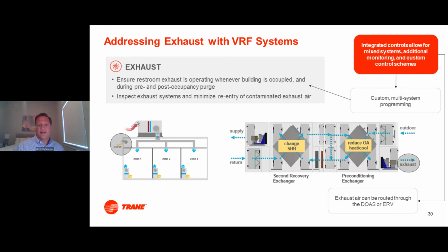When we talk about the next pillar, exhaust, how are we going to ensure that we're getting the bad air out of our building? So one piece of the guidance here is to ensure that our restroom exhaust is operating anytime a building is occupied and during pre and post occupancy purge. Again, if you don't have this tied into your control system, that can become difficult to do. Some buildings we work with have the restroom exhaust tied to a light switch. And so the guidance is basically going to be leaving that on almost all the time.